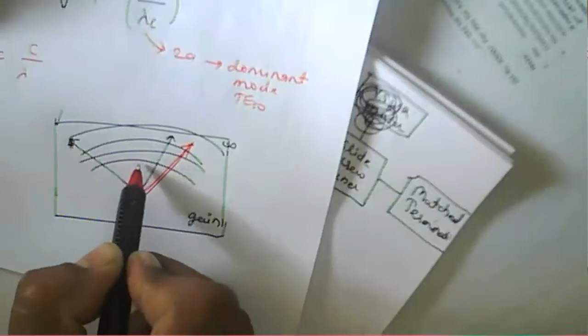Once it is at 1 using the gain control knob, then move the slotted section probe carriage toward the load or toward the generator, and we'll get the deflection. Then when we move toward the generator, at some moment the pointer will deflect maximum. Again, we move the probe, and then the pointer will start moving toward this particular direction.